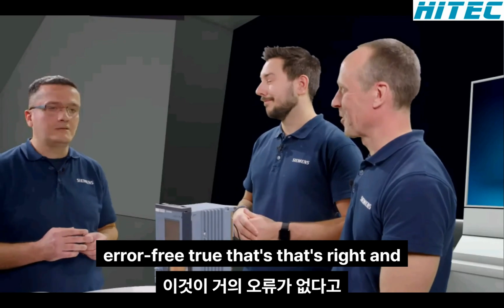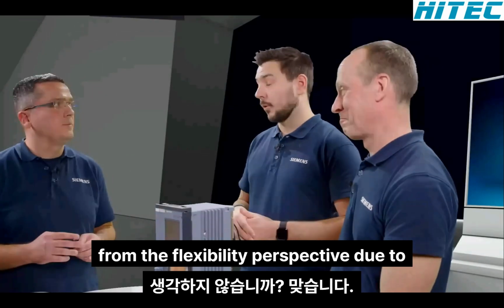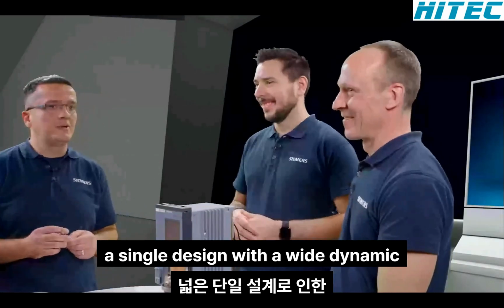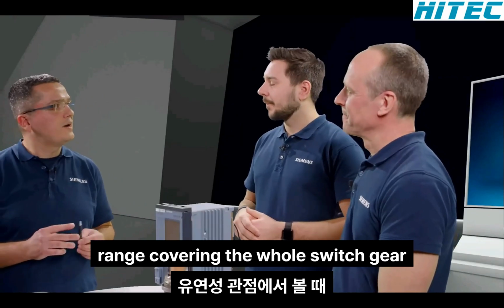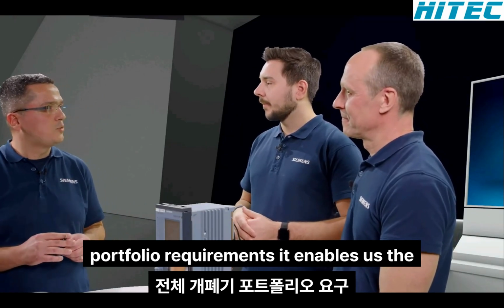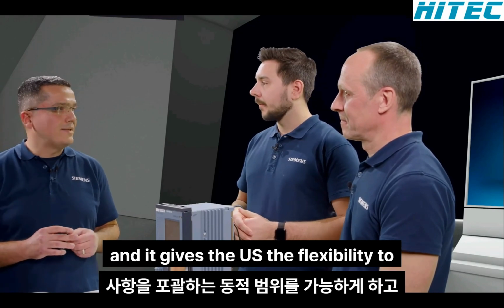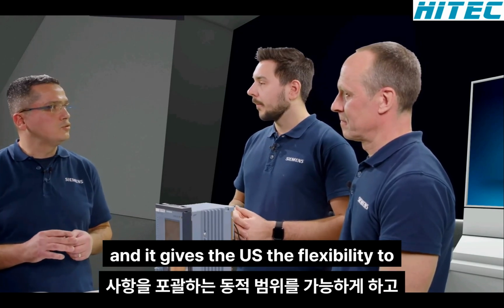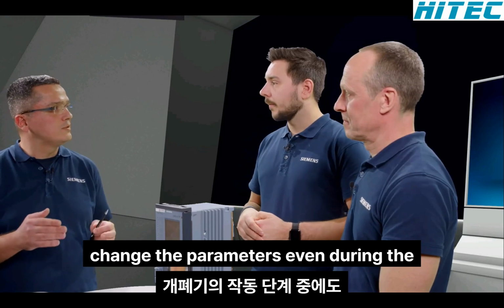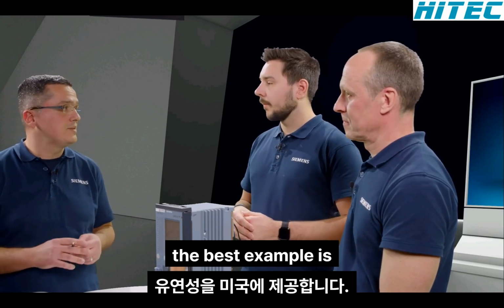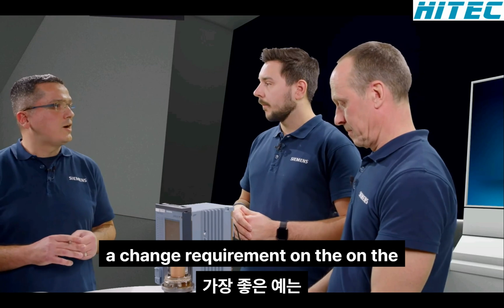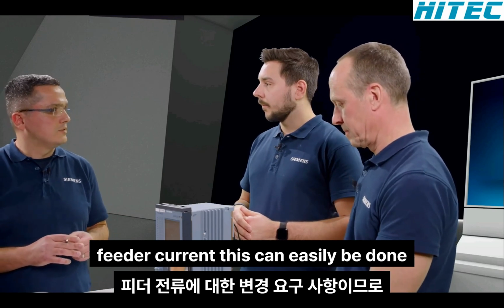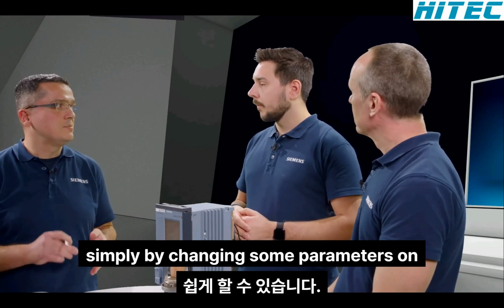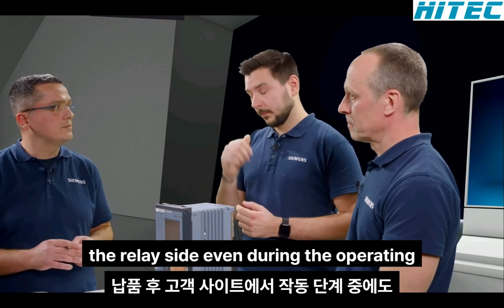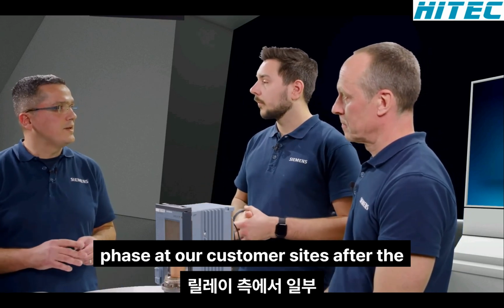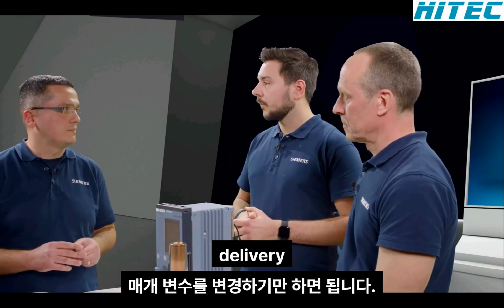True. That's right. And from the flexibility perspective, due to a single design with a wide dynamic range covering the whole switchgear portfolio requirements, it gives us the flexibility to change the parameters even during the operating phase of the switchgear. The best example is a change requirement on the feeder current. This can easily be done simply by changing some parameters on the relay side, even during the operating phase at our customer sites after the delivery. Yeah.